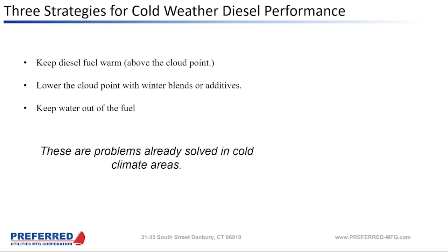There's basically three strategies for cold weather diesel performance. One is keep the diesel fuel warm. Keep it warm above the cloud point, or if there's going to be water in the fuel, it's got to stay warm above 32 degrees F. You can lower the cloud point with winter blends or additives. And then, like Alex was saying, it's important to keep the water out of the fuel, because if your fuel has a lot of water in it, then your lower temperature limit becomes 32, not the 14 to 18 that's normal for ultra low sulfur diesel to actually gel.